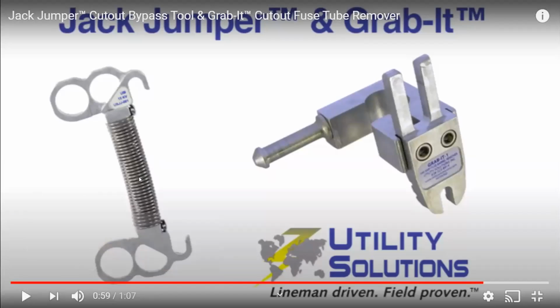As with everything out there in the world, there's two kinds of ratings on this. I can read one, can't read the other. One is voltage, and the other, amperage. Go to the specified voltage, and not above it, that's written on the jack jumper. This one is 15 kV. The writing's too small for me to see right here, and don't go above the rating of the amperage value that's on it. Always read your equipment before you use it.